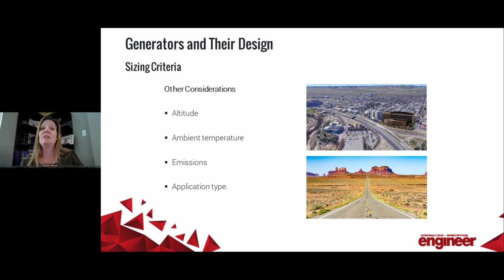In high altitude climates, the air pressure drop reduces the air density. So this can create problems with the generator if it's not properly designed to accommodate for it. Since the air is crucial for ignition in any type of generator, the low air density at high altitude could negatively impact that. So the generators that are properly designed for high altitude may have a larger fan to partially compensate for that reduced heat capacity, or they could be oversized to be able to run cooler under these conditions.